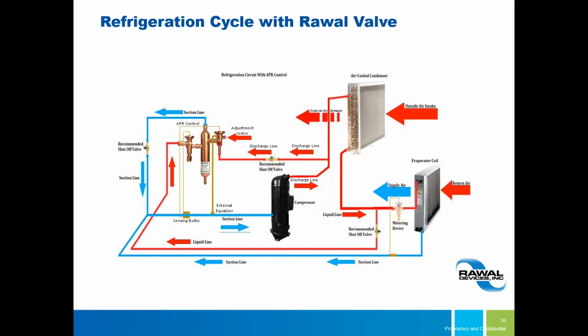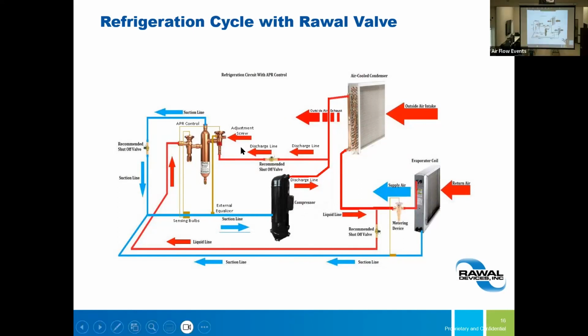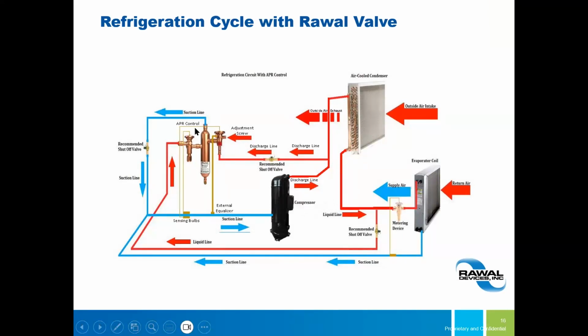Yeah, that's right. Okay. And then from there, you see the suction line off the top, so that you can run off the top here. And then obviously there's a shut off valve there because you can service it. And then it mixes there. And then obviously that suction line comes back into the compressor. And then you've obviously got some bulb sensors so that the Rawal valve and the compressor can kind of feel out and communicate back and forth about how to work together. And I hope I have done that. That's the best I could do with that, unfortunately, because I'm not a Rawal valve expert.